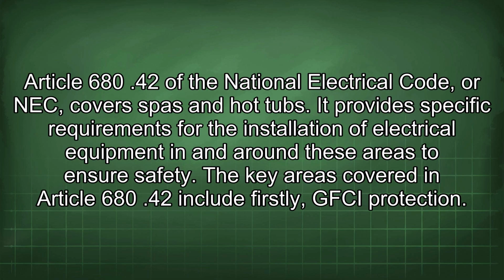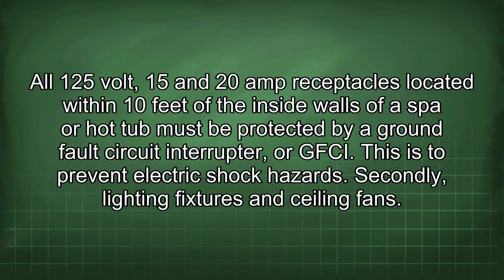Article 680.42 of the National Electrical Code, or NEC, covers spas and hot tubs. It provides specific requirements for the installation of electrical equipment in and around these areas to ensure safety. The key areas covered in Article 680.42 include, firstly, GFCI protection. All 125-volt, 15 and 20 amp receptacles located within 10 feet of the inside walls of a spa or hot tub must be protected by a ground fault circuit interrupter, or GFCI. This is to prevent electric shock hazards.